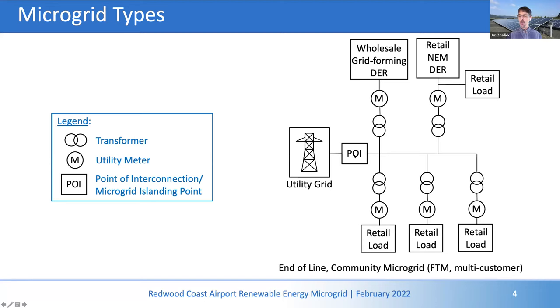So when this switch opens, there are a number of retail accounts - there may be numerous accounts off of a given transformer, or a transformer per account, but you see a transformer, a customer meter, and a bunch of different accounts with retail load. You might also have both wholesale DERs and retail NEM DERs. The retail NEM DERs are behind a retail meter along with retail load, while a wholesale grid forming DER is also behind a meter, but for wholesale participation, not retail.